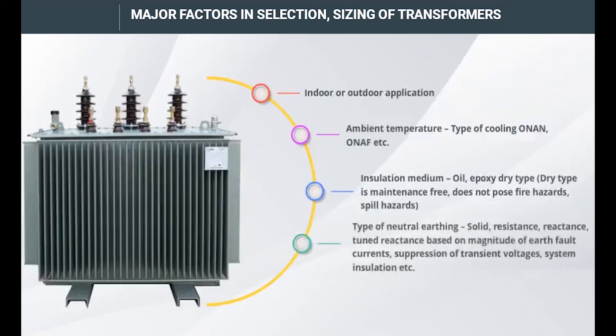The type of neutral earthing must be specified: solid, resistance, or reactance. A tuned reactance can be selected based on the magnitude of earth fault currents, with the aim of suppression of transient voltages and proper system insulation.